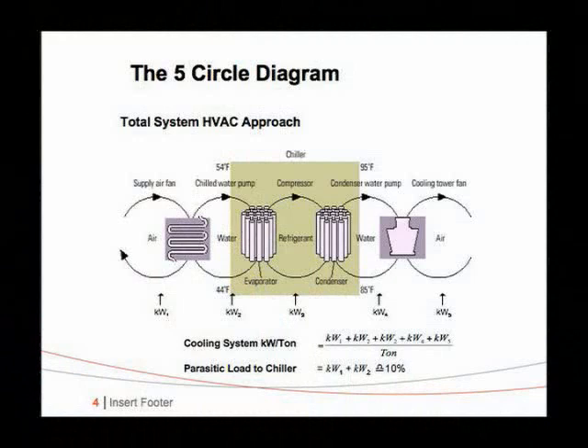If you look at the system for air conditioning or process cooling, you start on the left. You have an air loop, which is typically air handlers, which I can hear here, or fan coil units. You use air as a medium of transport to move clean air, to remove humidity, to remove temperature rise. You do it through a heat exchanger, which is typically a coil with water. To move the air, you need kilowatts in the fan, although there are passive systems that don't use this. You transfer the heat to a loop of water, typically.